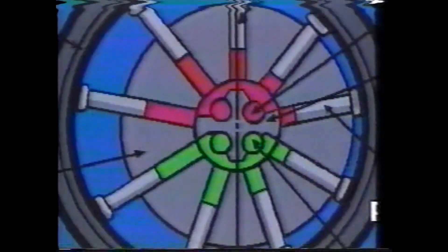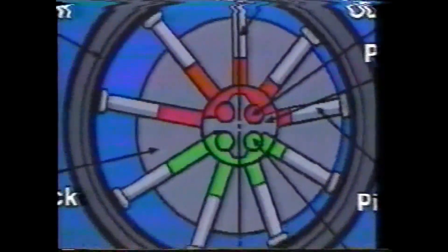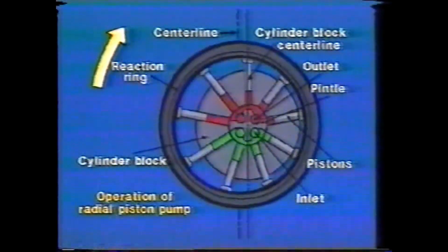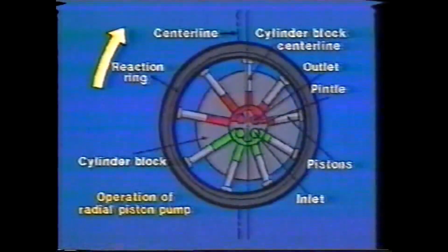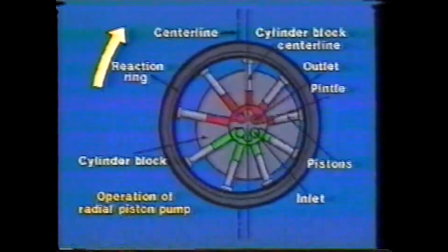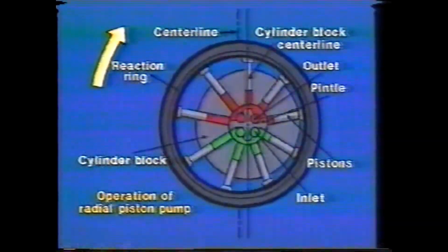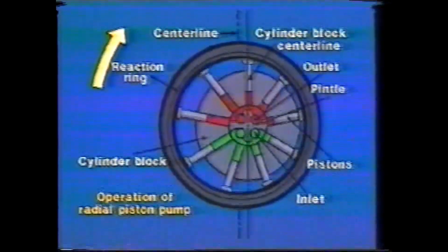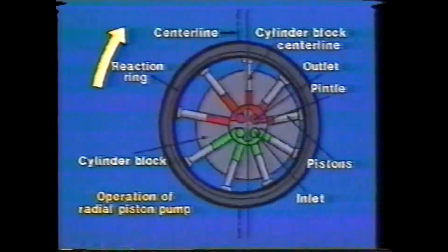A radial pump has pistons which reciprocate radially in a cylinder block that rotates on a stationary pintle, and inside a circular reaction ring. Some force, usually charging pressure and/or springs, holds the pistons out against the inner contour of the ring. With the ring offset from the center line of the cylinder block, the pistons reciprocate in their bores, taking in and expelling fluid through porting in the pintle. Moving the reaction ring will change the length of piston travel, thereby varying the pump displacement and output flow.